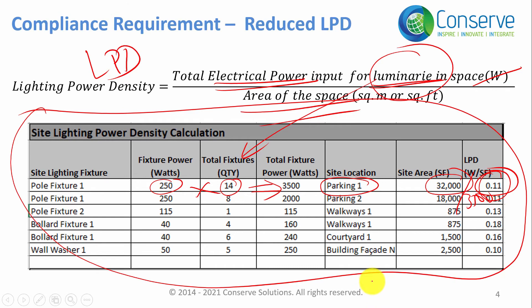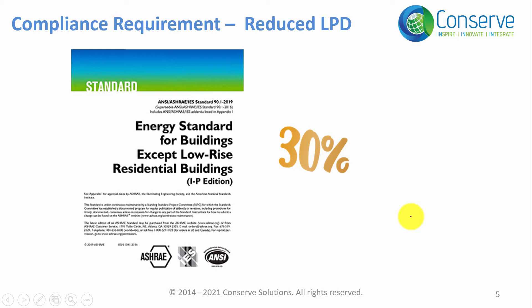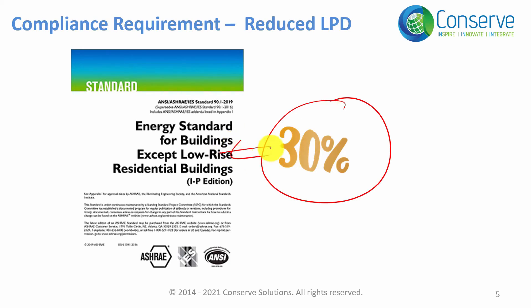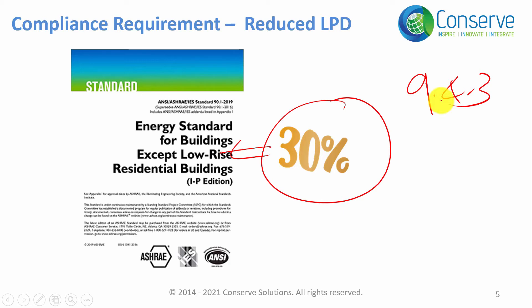To reduce light pollution, the Lighting Power Density should be minimized. The compliance requirement for this credit is that the LPD must be 30% less than the value prescribed by ASHRAE 90.1-2010. Specifically, ASHRAE 90.1-2010 Table 9.4.3 gives the lighting power allowance for exterior spaces, and the project LPD must be 30% below that standard value.